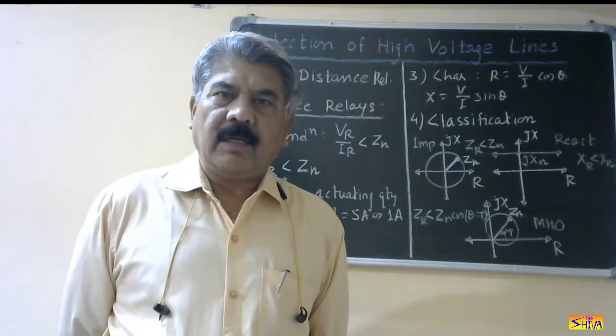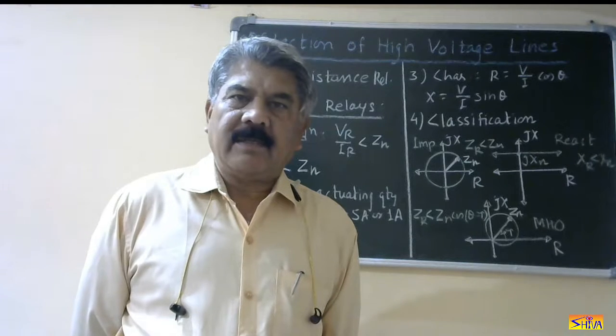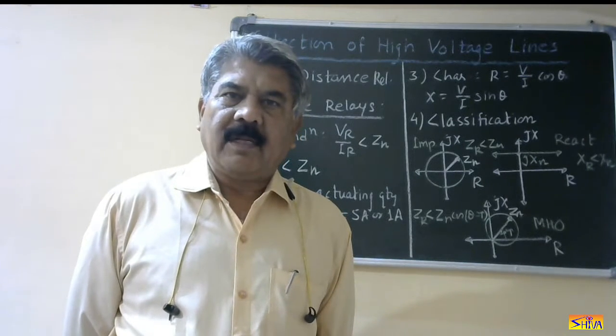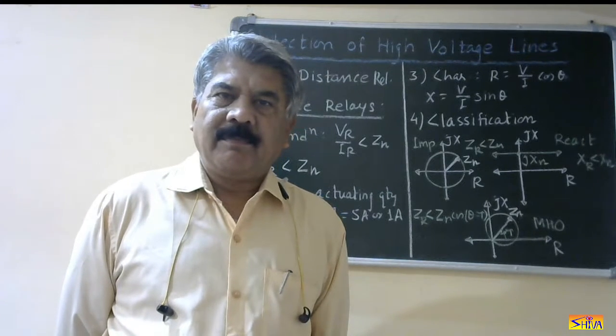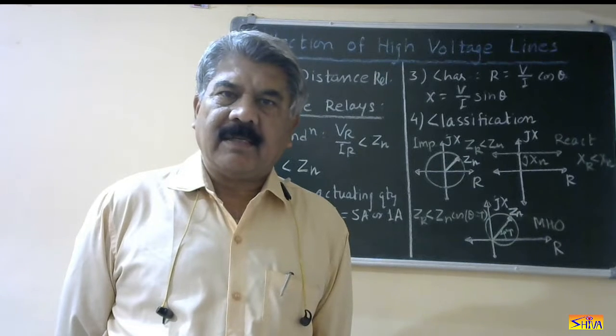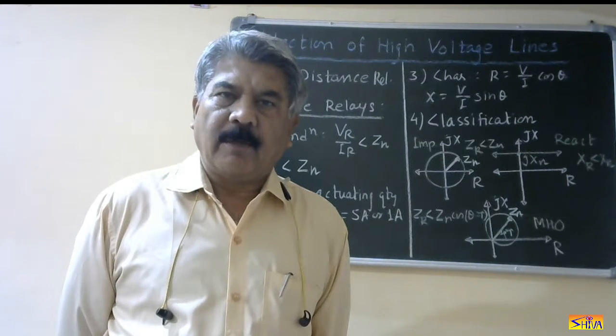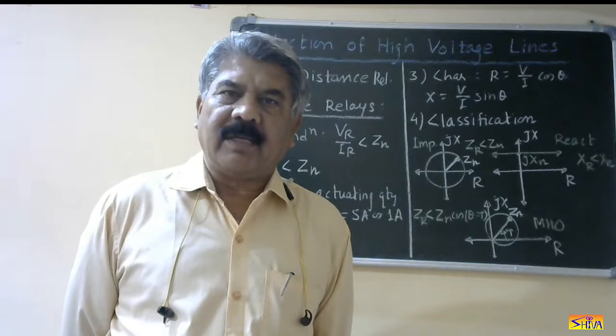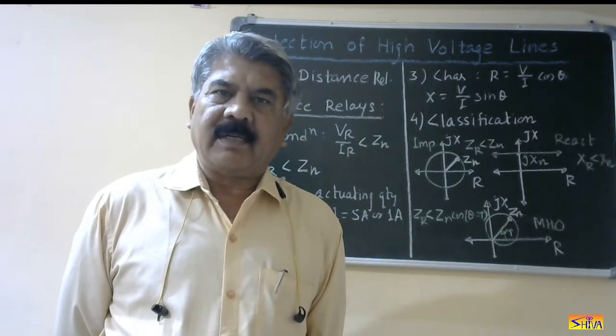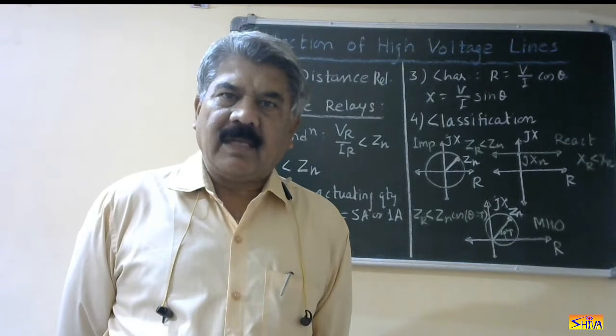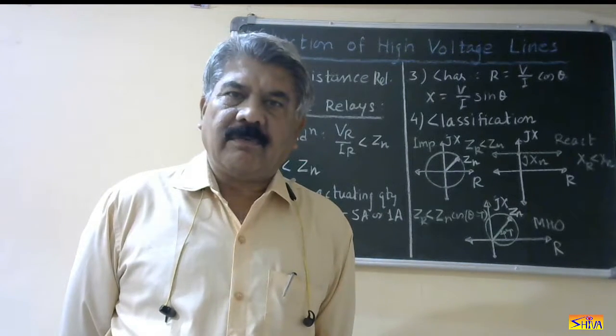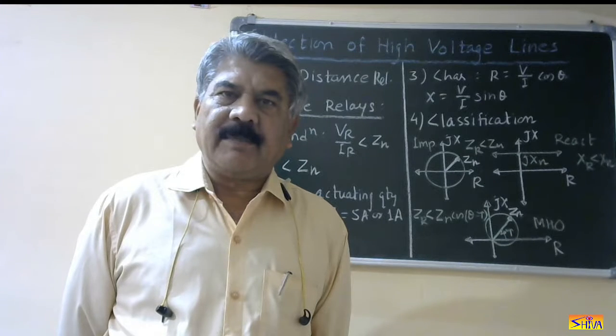Hello friends, good morning. In my last to last class, I had explained the limitations of overcurrent relays. The limitations were basically that operating time is relatively large, and the operating time depends on the magnitude of the current, which is affected by location of the fault, type of the fault, fault impedance, and generating conditions. Therefore, the application of overcurrent relays is limited to low voltage lines, that is distribution lines only.